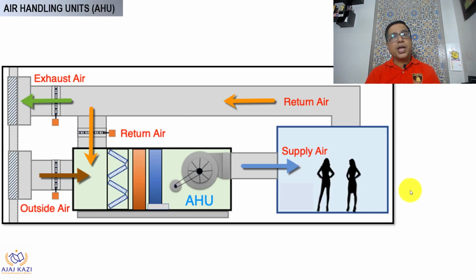This is again a representation. This is an AHU. It supplies the air. The supply air is cold, and it becomes heated up because it takes a lot of heat from the space, from the lights, from the people. That becomes the return air. Part of it goes out and most of it comes back as return air. We also add fresh air as outside air to dilute the VOCs and the inside conditions, so that we get a lot of freshness from the fresh air.